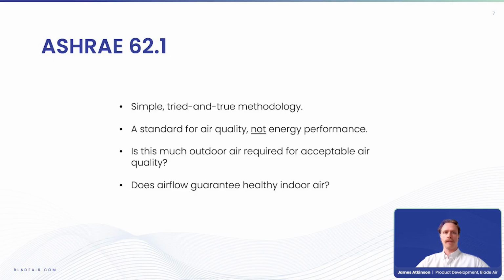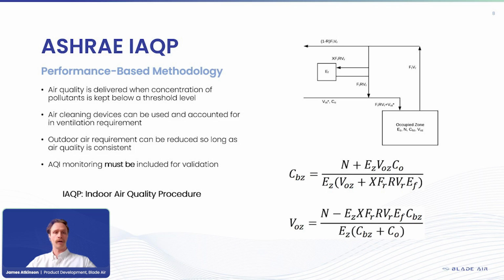So how do we guarantee healthy indoor air and how do we guarantee better energy savings? This is where the IAQP, or the Indoor Air Quality Procedure, comes in. It looks like a bunch of scary math, scary numbers, a lot of subscripts, a lot of variables, but it really boils down to a mass balance equation. There are pollutants being generated and pollutants being removed. Pollutants are removed by air cleaners and ventilation, and pollutants are generated by people breathing, activities like cutting and machining, cleaning products, and off-gassing of your building components. So you're really just solving that mass balance equation to keep pollutants under a required threshold level that has been determined to be safe for your occupants.